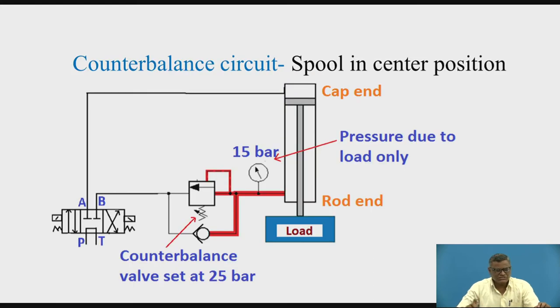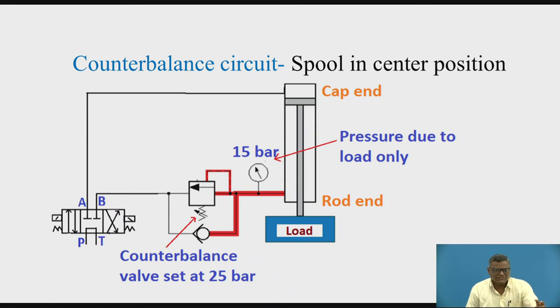Now let us go to the counterbalance circuit. The spool is in the center position. We have introduced the counterbalance valve here. The counterbalance valve also belongs to the pressure control group, and it is also a normally closed valve, going to open when a certain pressure is reached, where we have the setting of that one.